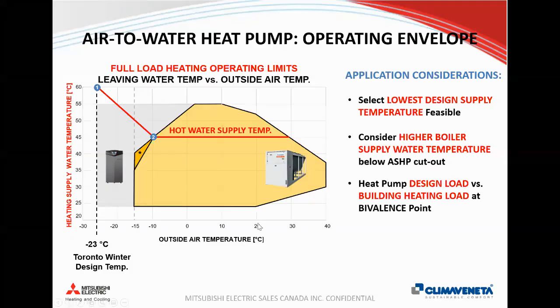So one strategy that you can look at for heat pumps is, if you're sizing heat emitters in the building and you think that 45 degrees Celsius is too cold to use, you can do a capacity check. You can still select your coils for a hotter supply temperature of, say, 60 degrees Celsius in this example. And as it gets warmer outside, you can decrease the temperature and just verify that you have enough capacity to work with the supply temperature available at the cutout temperature where you want to use the heat pump. So in this example, you check the heat load for the heat emitters at 60 degrees Celsius for your design conditions, verify that you can match the heat load at that operating point. And then for running off the heat pump at minus 10, chances are you have less of a heat load required in the individual spaces, so you can see what capacity you have with a lower water temperature from the heat pump and verify that it'll still meet those needs. And then that means that you can essentially run off the heat pump as long as it's warmer than your design selection point for the heat pump.